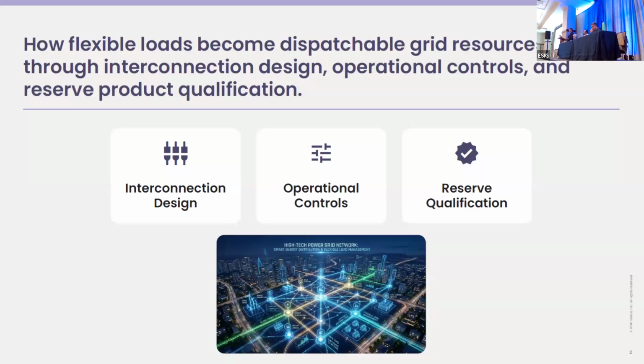All of this is based around the fundamental thesis that it is better to do flexibility on the front end than the back end—not that there can't be some flexibility achieved with legacy assets, but it's all going to be a lot easier if you have something built to accommodate this from the start, going through the interconnection process and designing operational controls baked in for what the hardware is capable of, what the market rules are, and what the local grid topology would require.